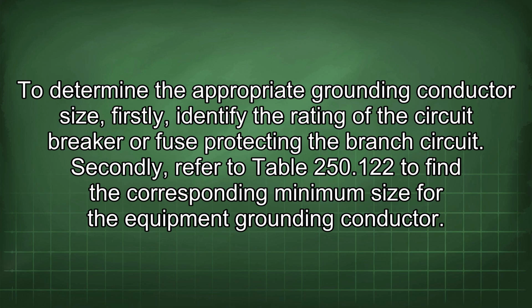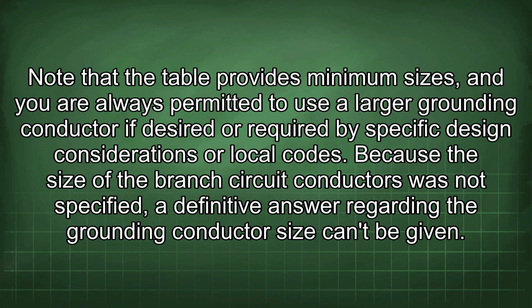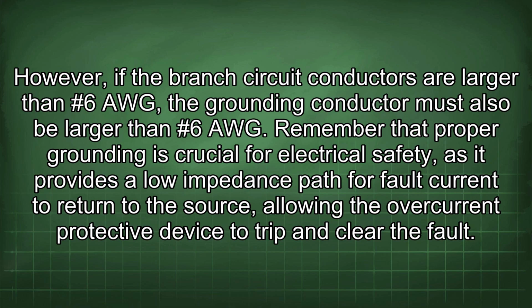To determine the appropriate grounding conductor size, firstly, identify the rating of the circuit breaker or fuse protecting the branch circuit. Secondly, refer to Table 250.122 to find the corresponding minimum size for the equipment grounding conductor. Note that the table provides minimum sizes, and you are always permitted to use a larger grounding conductor if desired or required by specific design considerations or local codes. Because the size of the branch circuit conductors was not specified, a definitive answer regarding the grounding conductor size can't be given. However, if the branch circuit conductors are larger than #6 AWG, the grounding conductor must also be larger than #6 AWG.